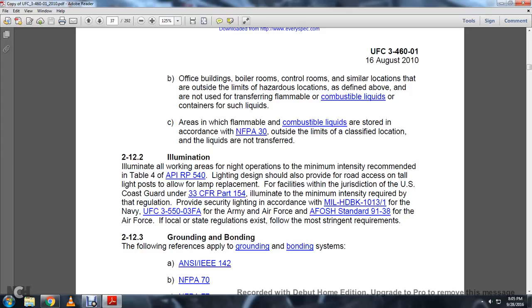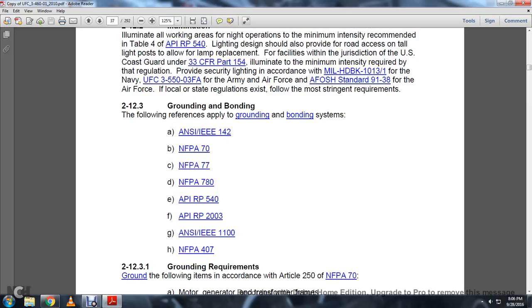2-12.2 Illumination. Illuminate all working areas for night operation to the minimum intensity recommended in Table 4 of API RP 540. Light design should also provide road access to the light tail to allow for lamp replacement. For facilities under the jurisdiction of the U.S. Coast Guard under 33 CFR Part 154, provide the minimum illumination intensity required by the regulation. Provide security lighting in accordance with Military Handbook 1013-1 for the Navy, UFC 3-550-03FA for the Army, and AFOSH Standard 91-38 for the Air Force. If local and state regulations exist, follow the most stringent requirements.